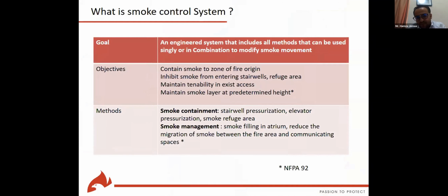What is smoke control? Smoke control system is actually an engineering system using methods that can modify the movement of the smoke inside a building. Methods of the smoke control as per the NFPA 92 can be smoke management, which is related to controlling the smoke inside atriums, and smoke containment related to the stairwell pressurization, elevator pressurization, and the smoke refuge area. The main objective of a smoke control system is to contain the smoke inside the original fire zone and inhibit the smoke from diverting or from entering stairwell and refuge area. Also maintaining a tenability in exit access and maintain smoke layer at the predetermined height.